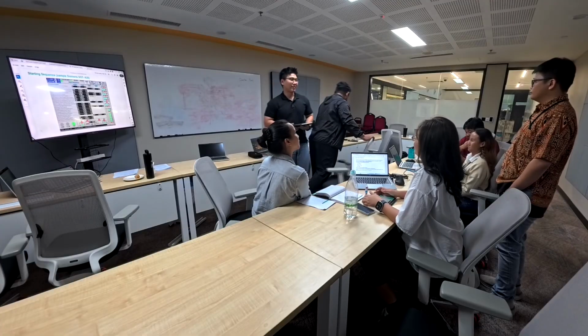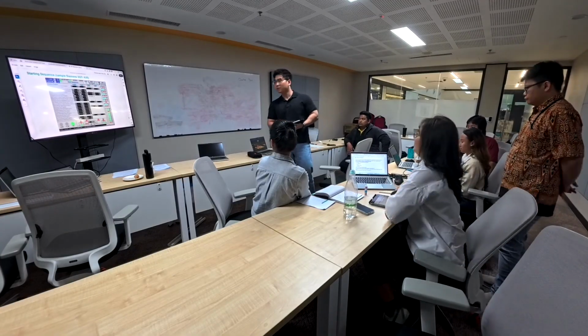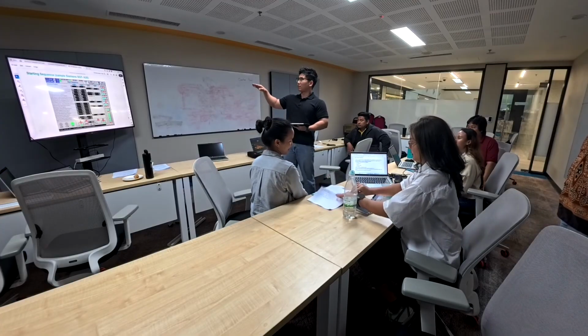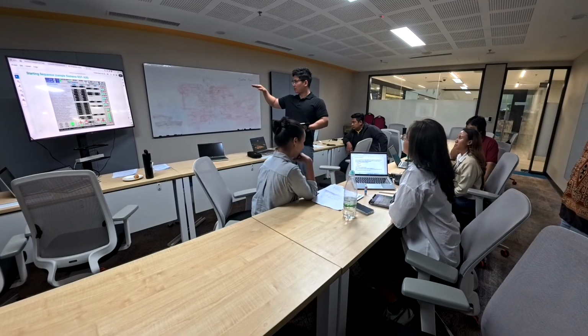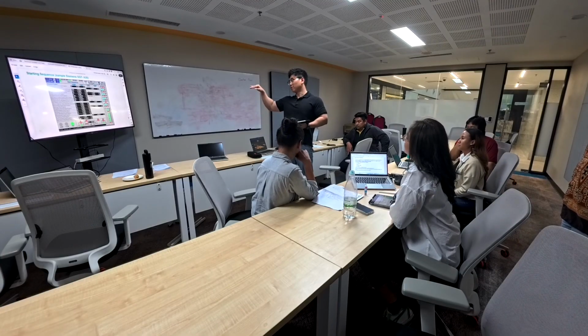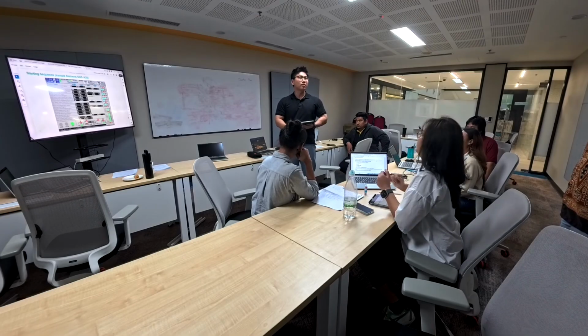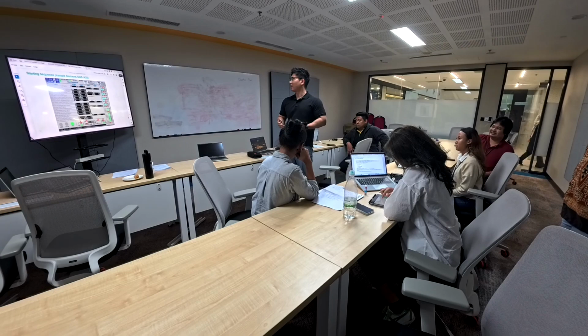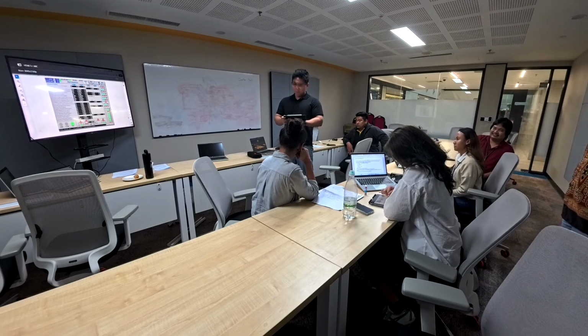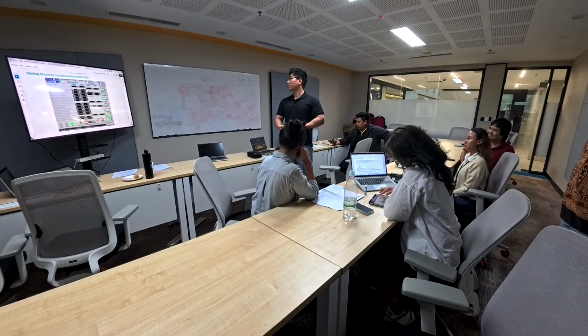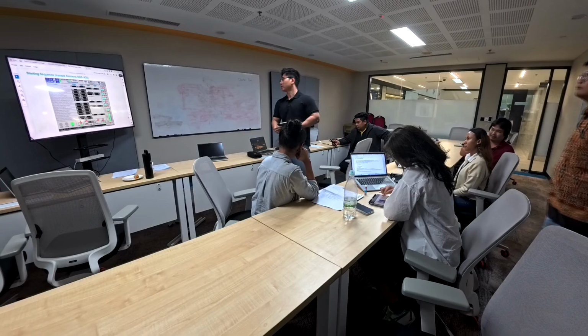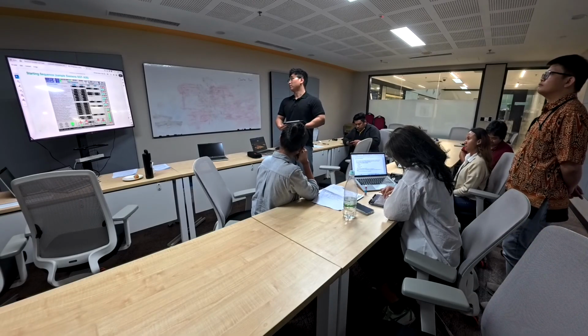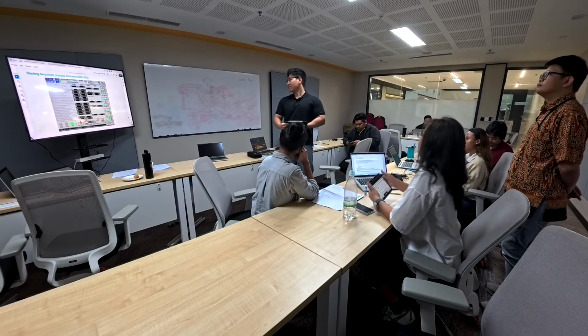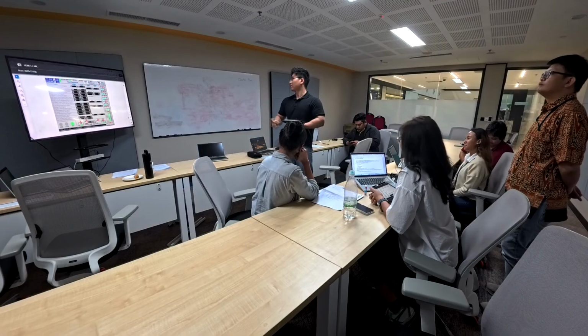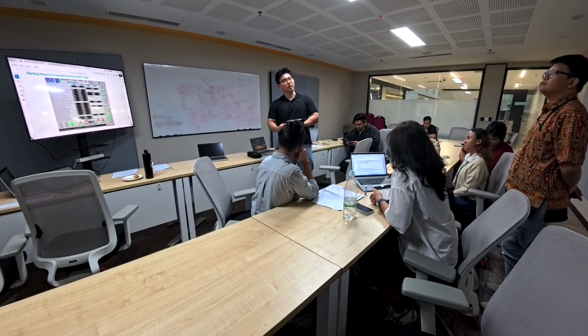Okay, Johnson. Okay, next is about starting sequence. So from this we can see that there are 22 starting sequences that the GG or GT has to follow. Sorry, for the gas generator to follow, lah, before it is fully started. And similar to the starting permissive just now, we have to achieve the required parameters during the starting sequence timing to proceed to another step. If the timing is not achieved, then there might be some problem, and you have to check over there.